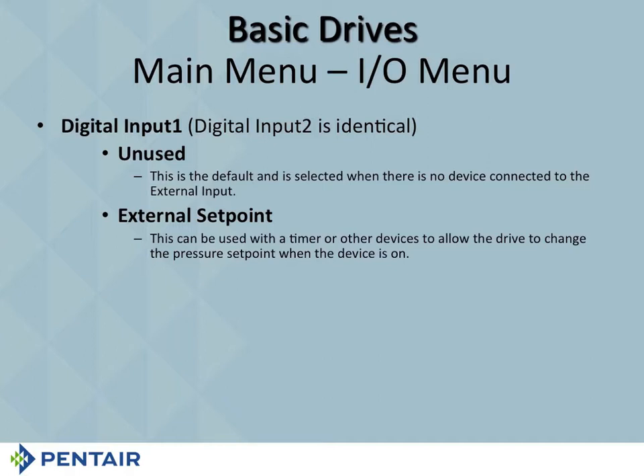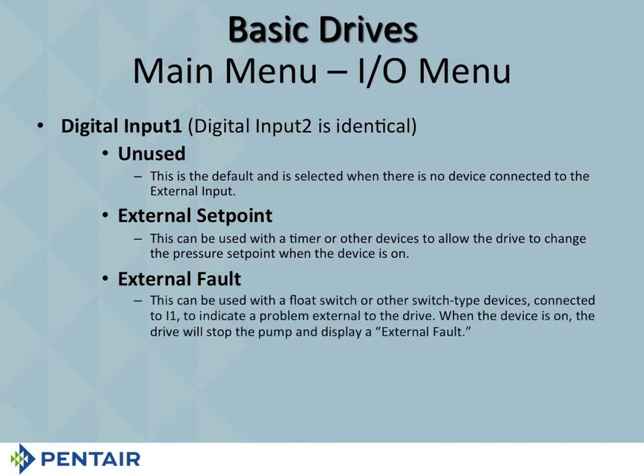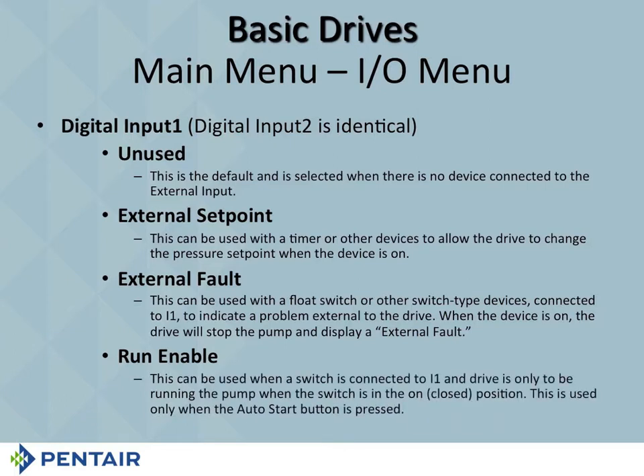You're going to run your timer from your sprinkler system over to one of your digital inputs, and you're going to set that digital input for external set point. All right? Remember, external fault basically says, I want the drive to turn off. So you can take digital input 2, and you can hook up a moisture sensor. You can hook up a float switch on a cistern, so that when the cistern gets too low, the pump will turn off. Or you can do it the other way. Run enable. Hook up that cistern that says, I don't want this thing to run until there's enough water in there, and so the float has to be on to do that.